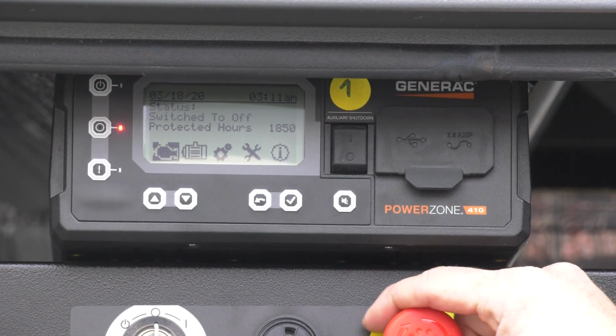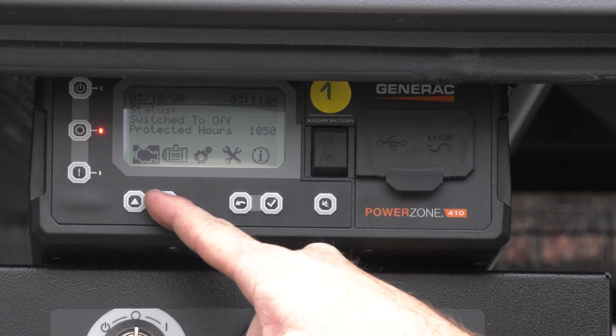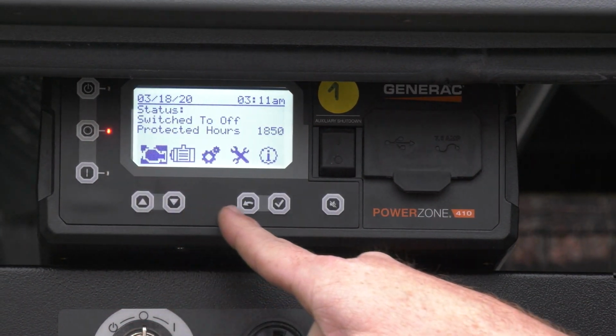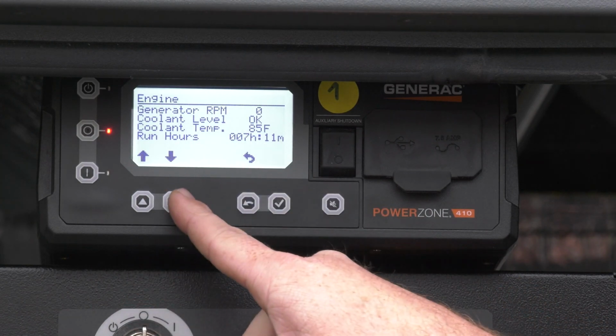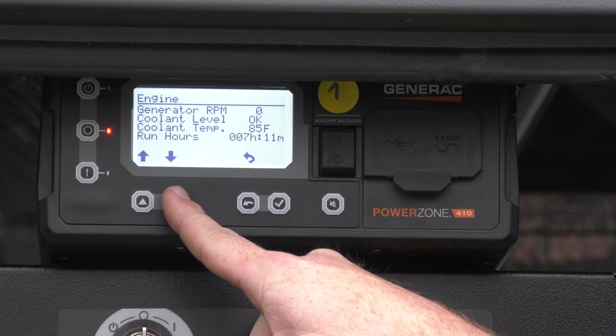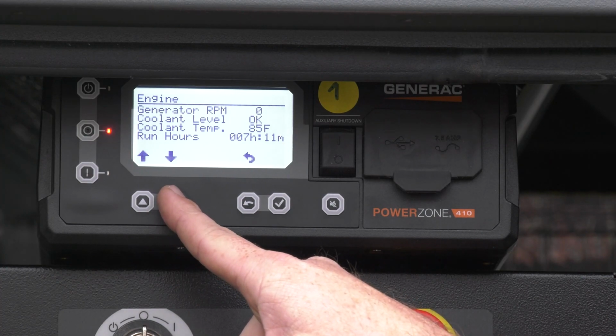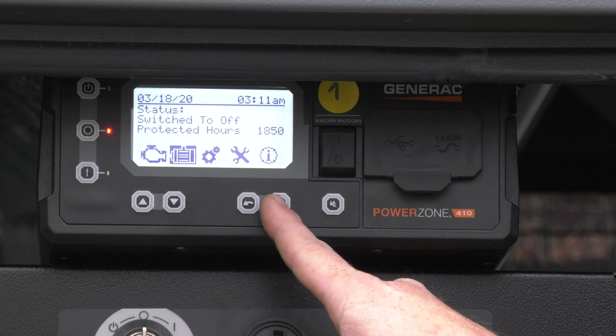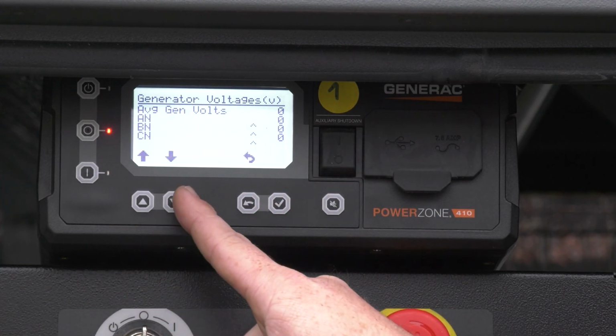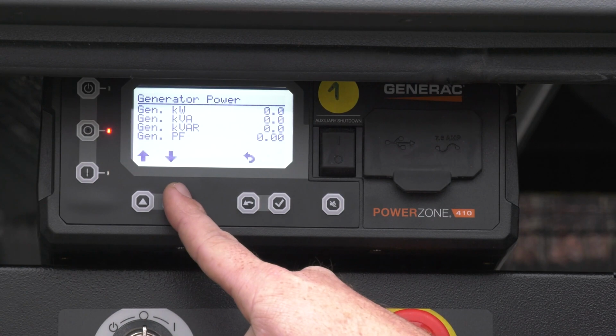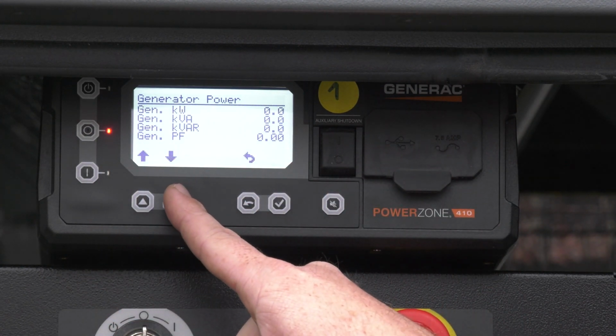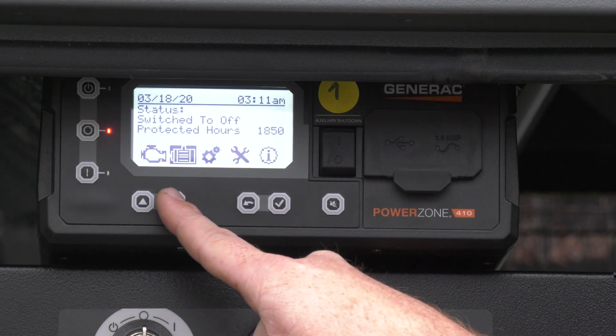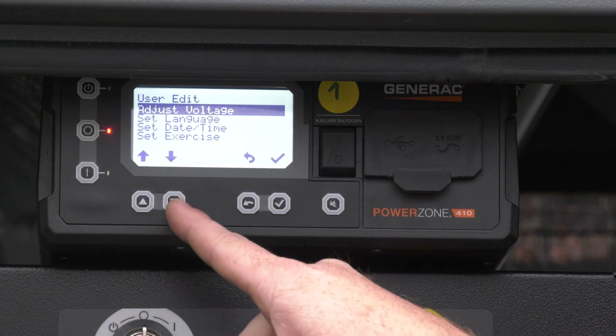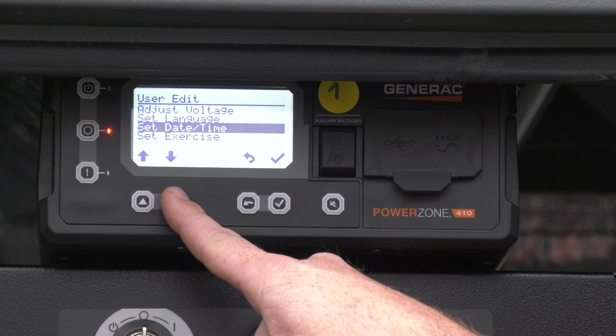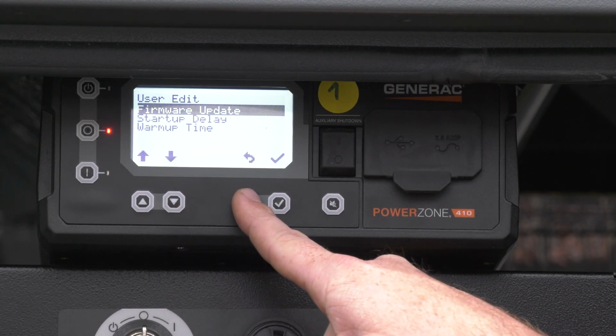You have an auxiliary e-stop, an auxiliary shutdown. Menu's all the same. That's your engine, which gives you all your basic engine information: RPM, coolant level, oil temperature, your run hours, all the basic info. You can scroll back out of that, go to generator. It gives you your generator voltage when it's running, your amps, your KW, KVA, power factor. You can scroll back over. This is the settings menu for adjustments in voltage, date and time, exercise, all that stuff.